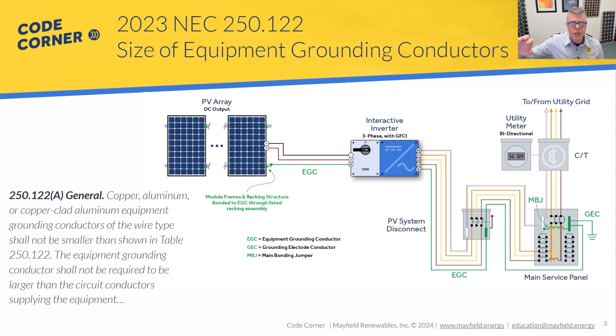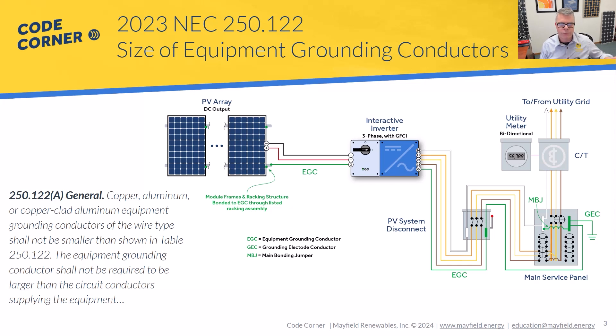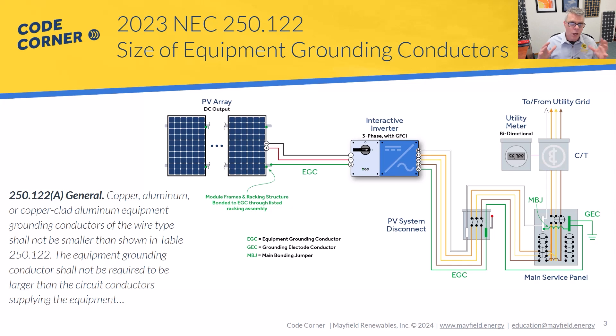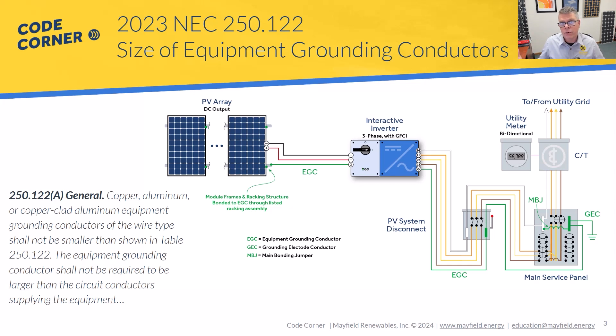Section 250.122(a) covers the types of equipment grounding conductors, and 250.122(b) talks about the increase in size. If it doesn't click, read 250.122(b) — it says if you increase your conductor sizes you have to increase the EGC — and then 690.45 says for PV systems you actually don't have to do that. A big part of the reason is that PV systems are current-limited; we don't have an infinite amount of current behind our sources, so upsizing the EGC doesn't do much because the available fault currents simply aren't that high.